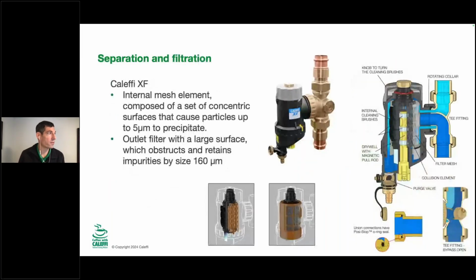This is a little bit of both. This is a device that we make, the XF, that is a dirt separator in the same way that I've described, but also has a Y strainer, essentially a mesh strainer, in there. You can rotate that gray knob at the top and it uses a bristle brush to wipe it clean, and then you can blow it down. So this is for really high performance dirt separation with a magnet in it as well. We developed these for heat pumps, with really small heat exchanger passages and existing systems. That's what we intended there. So, best case scenario for dirt separation and straining.